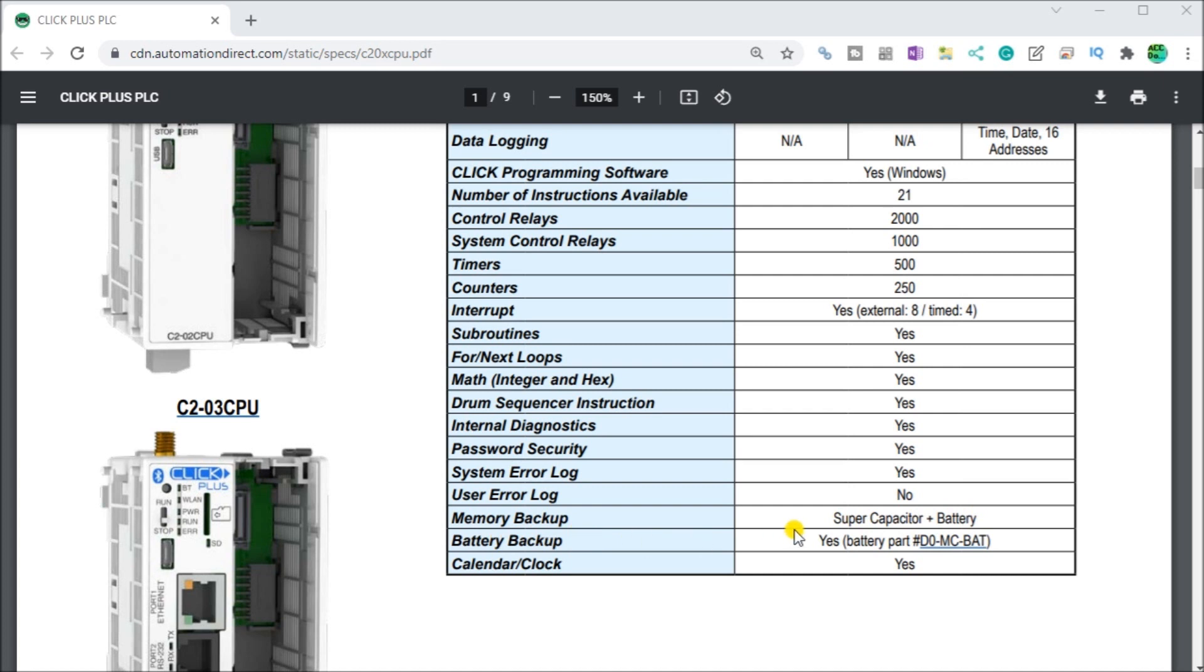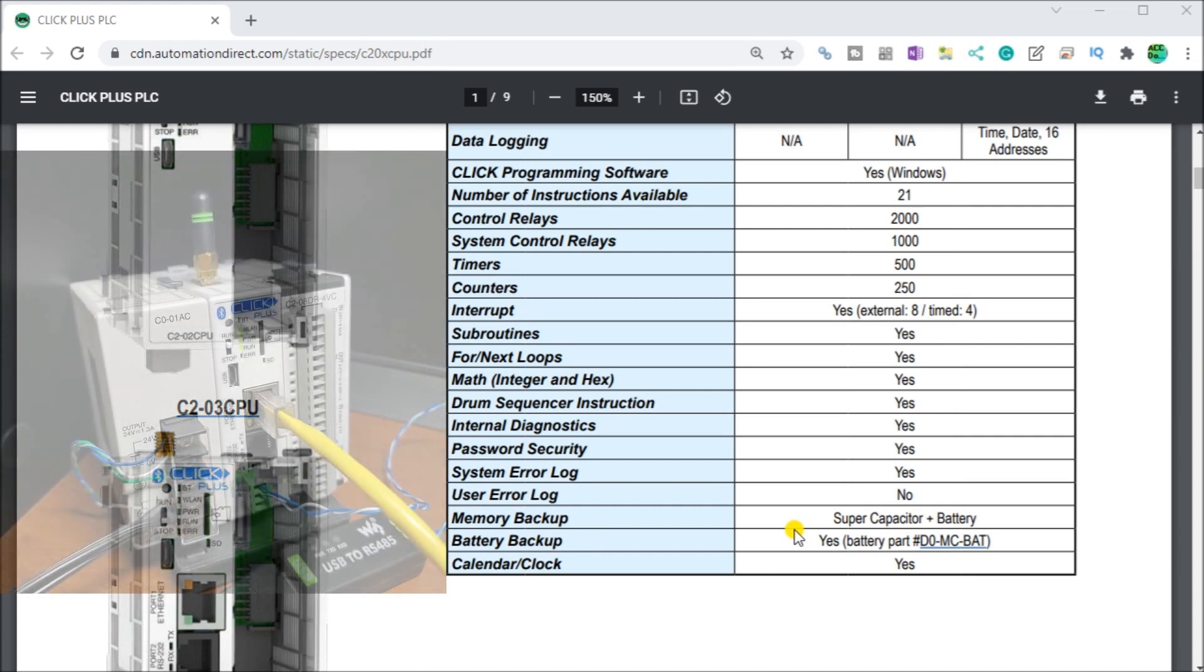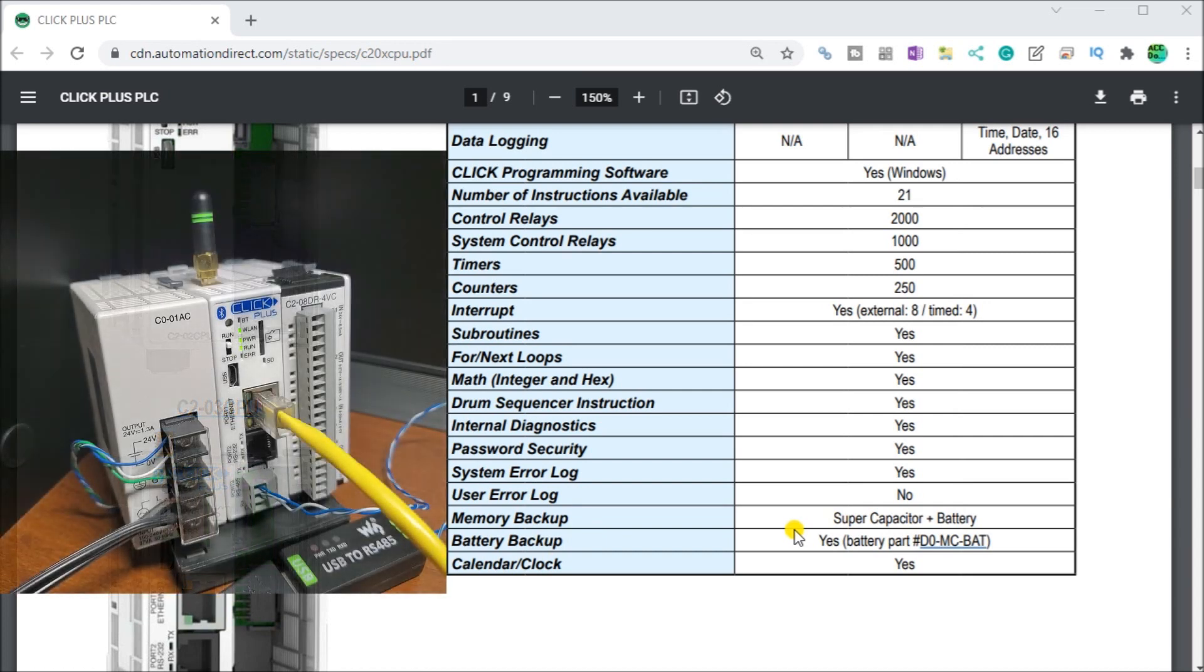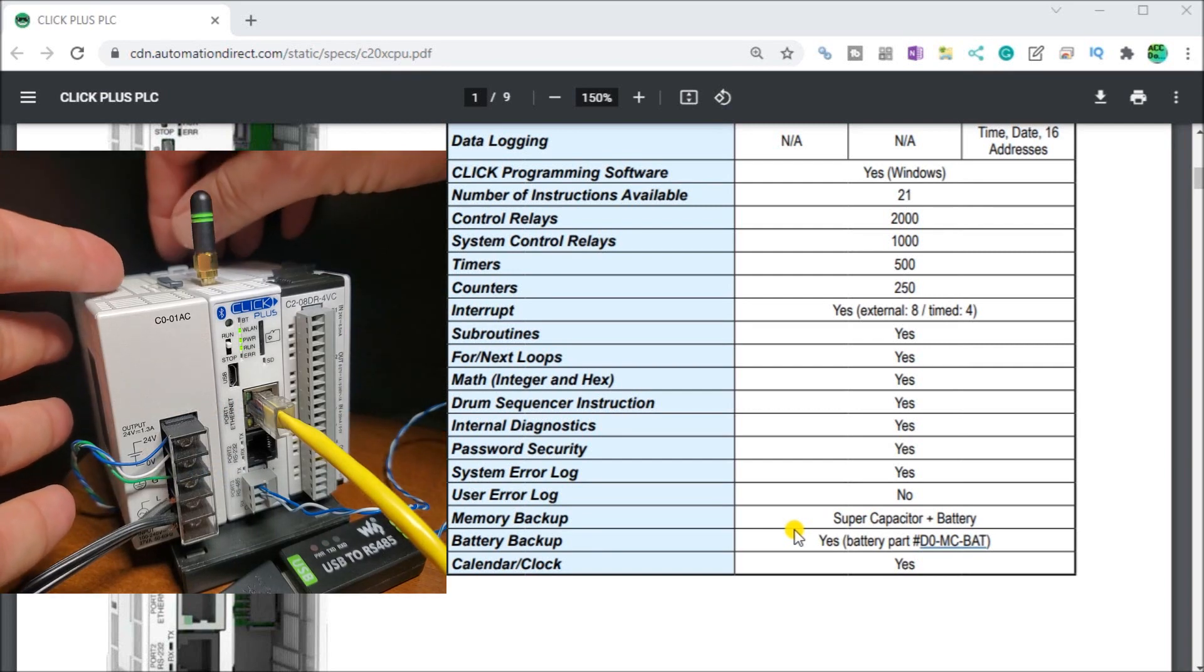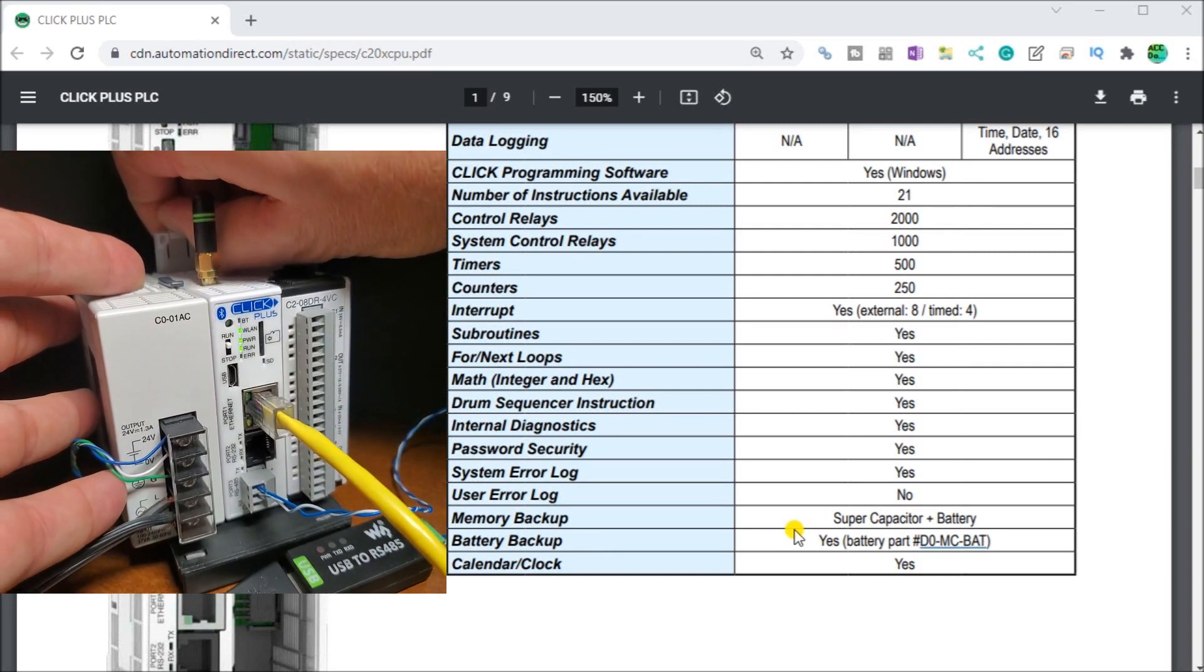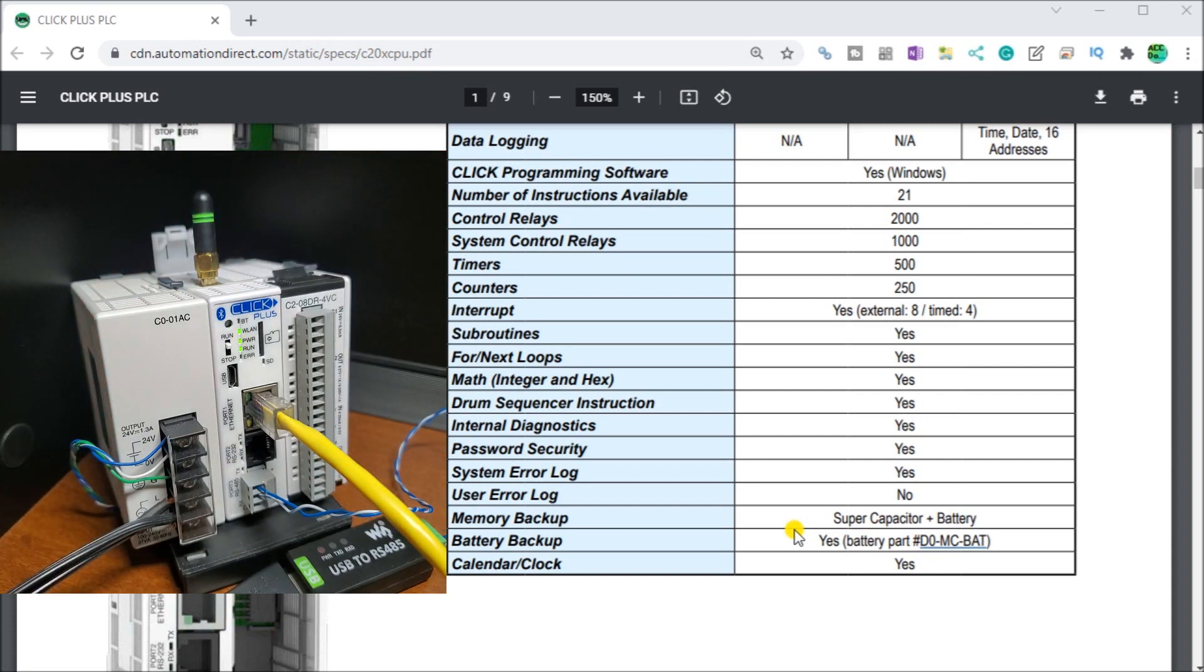Looking at our physical hardware now, here is our Click Plus PLC. If I were to open up the battery compartment, this is where I would actually put my battery in here to store it. Currently right now this controller does not have a battery in it, so I have one hour when I remove power to ensure that I put power back on or I will lose some of my data memory or data values. So what I have to do as a programmer is to make sure that I'm not using that memory area.